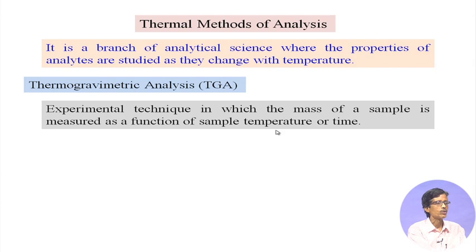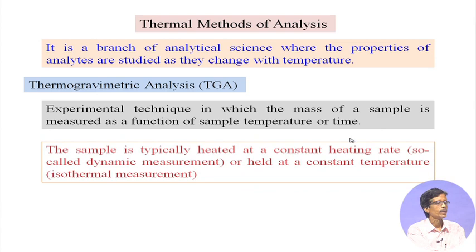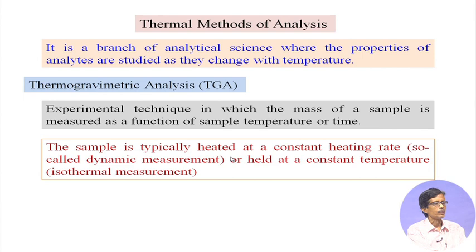We can monitor mass loss with temperature rise, and sometimes when cooling in reverse there can be mass gain. The heating rate of the furnace holding the sample over the balance is synchronized with the temperature rise, so we can also plot against time. We can heat the analyte at a constant heating rate — say 5°C per minute or 10°C per minute — which is called the dynamic measurement.